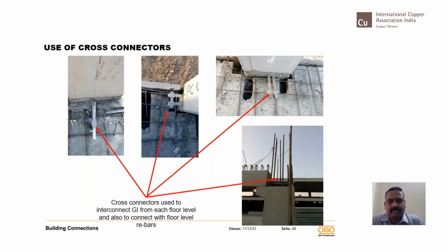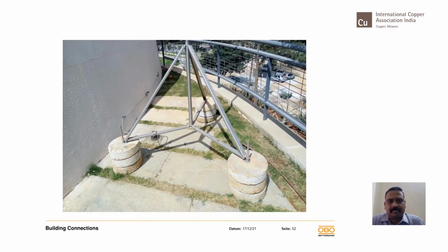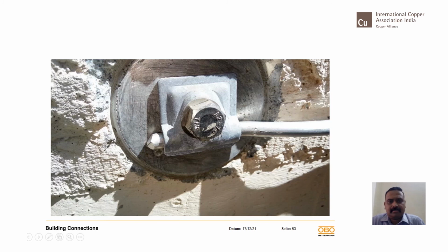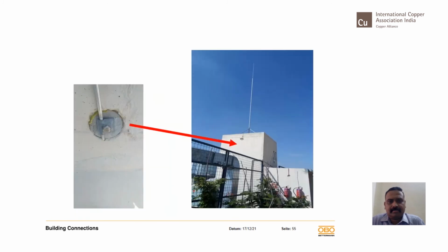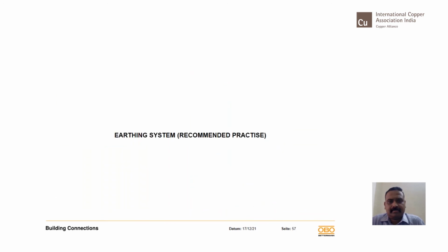So several floor levels are there. You can connect to the rebars at those levels also. And finally, when the concreting is completed, the earth fixing point will enable you to take a connection and connect to the lightning protection system here. This forms a complete installation, and you will not see any external conductors outside the building. The biggest advantage of this system is that you are using as many rebars as possible, interconnected inside, so that dispersion of current happens and the reduction of electromagnetic interference comes into effect.